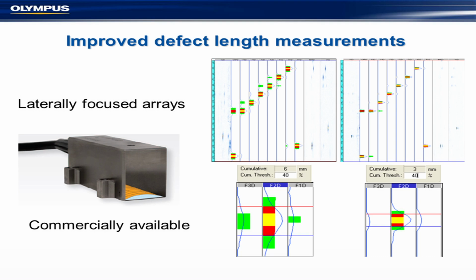Another thing we've developed is laterally focused arrays. You'll notice this one has a focus on it. The way ultrasound works, once the beam goes into the pipe it inherently defocuses, and the smaller the pipe, the worse the defocusing. It's not too bad on bigger pipes used for gas main lines, but on smaller pipes it becomes an issue. So we built arrays with a laterally focused range: we focused the inside, put a flat on it, and designed a wedge that's standard for everything else. So when doing replacements, you just pop on or pop off a smooth-faced wedge without running into problems.